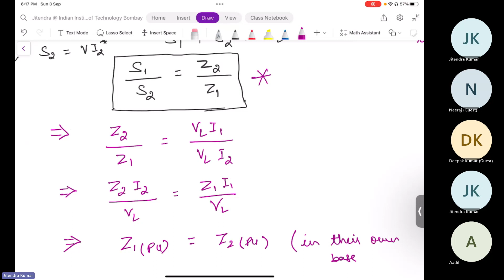Okay, so both will be equal. As soon as you see in the problem that load sharing is directly proportional to its kVA rating, you can immediately apply this expression. But you have to take care of one very important thing: both impedances must be in their own base. What do I mean by in their own base? That will be clarified in the problem.